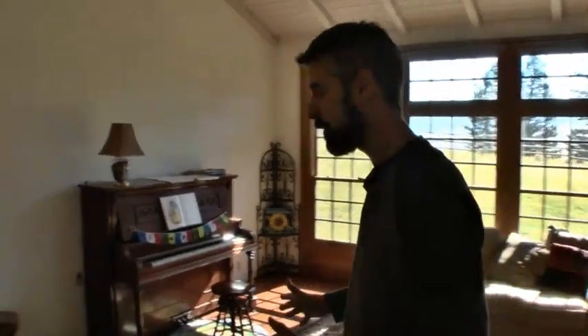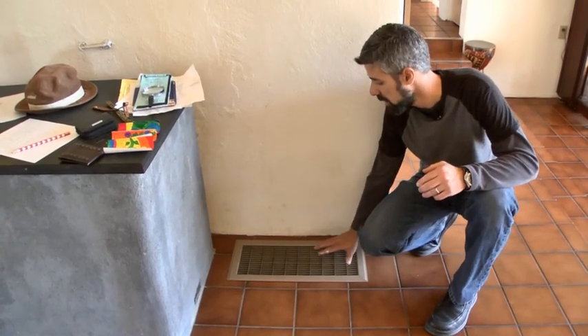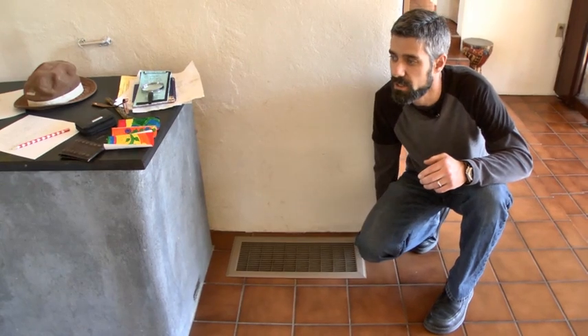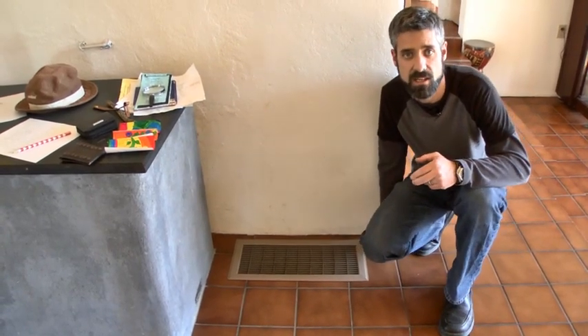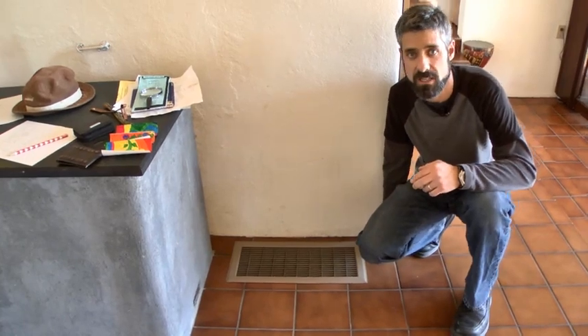What we're looking for are things we can fix easily to account for air loss — we're not necessarily looking for every single bit. Most states will allow for duct sealing regardless of what those CFM numbers are. I am feeling air coming out of some of this duct work, so we may have some duct leaks that could be fixed. If they're exposed down in the crawl space, that might be an easy thing to do.